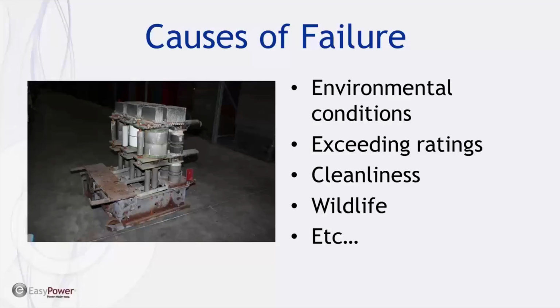Exceeding the ratings of the circuit breaker, cleanliness of the circuit breaker. I've personally seen 20-year-old distribution breakers that had failure, and when they opened the high voltage cabinet, the vacuum interrupters were completely covered in dust. And looking at the maintenance log, the high voltage cabinet hadn't been opened since it was originally commissioned 20 years before. So cleanliness is an important thing with regard to vacuum interrupters and making sure that they operate properly.